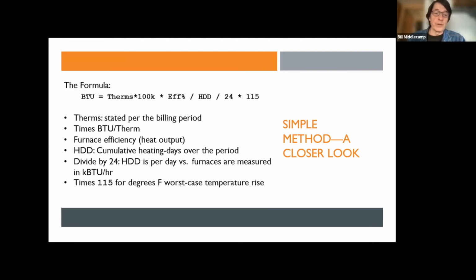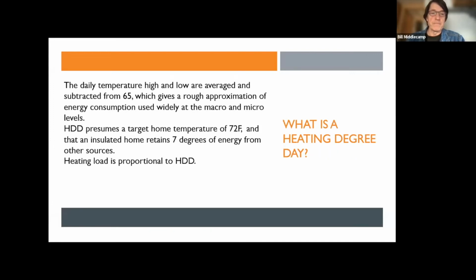Again, dividing by 24 because furnaces are measured in BTUs per hour. And this worst case temperature rise, like I said, was 50 degrees below 0 to 65 degrees above, 115 degrees of worst case temperature rise. My belief was that I would have the furnace running 100%. And if anybody opened a door, the temperature would drop and you'd have a hard time recovering. But we don't get temperatures like that. So this was my fudge factor, a safety margin to make sure that my furnace wasn't going to fall short of heating the house. Next slide, please.